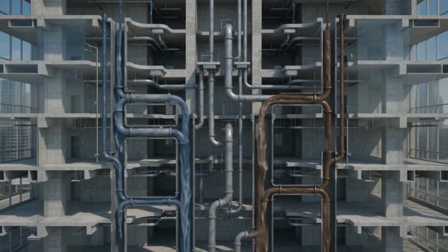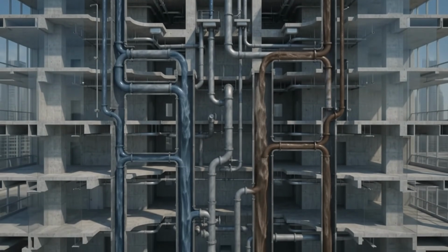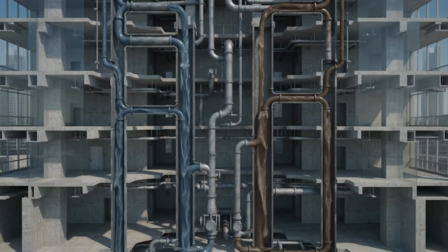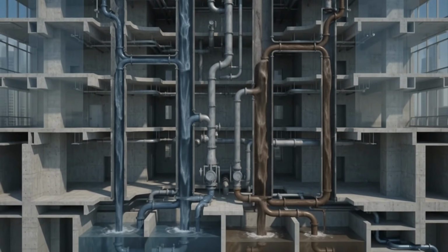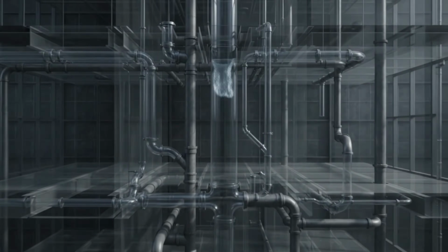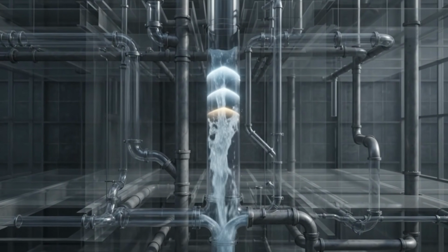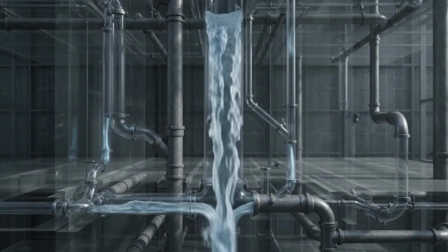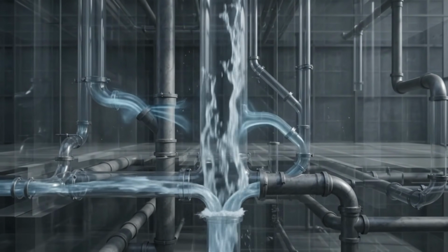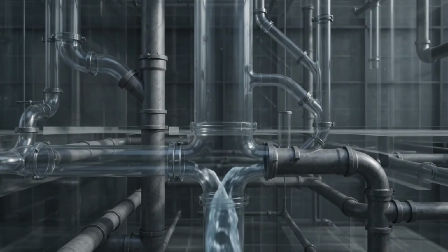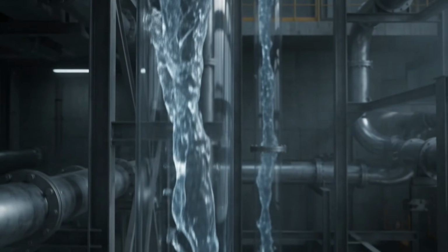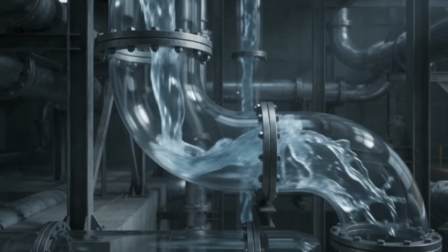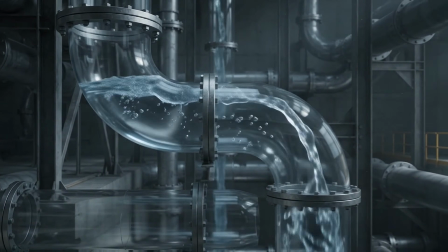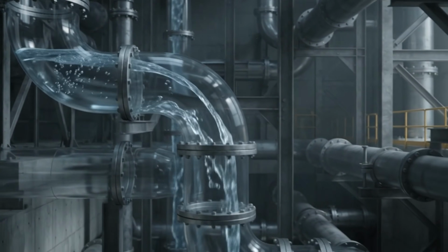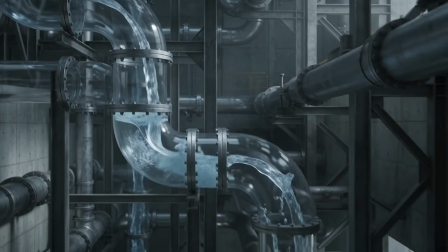What goes up must come down, and the building system must handle the unique hydraulic pressures of water falling from hundreds of meters above. When water falls from the 163rd floor, siphon vent stacks equalize air pressure ahead of the falling column, preventing dangerous vacuum effects. Engineers placed offset bends at strategic intervals in the drainage stacks, each one breaking the velocity of falling water, dissipating energy, and protecting the pipe from impact damage.